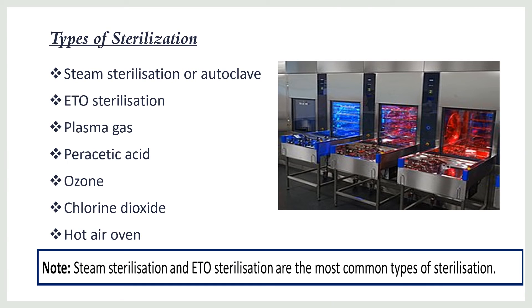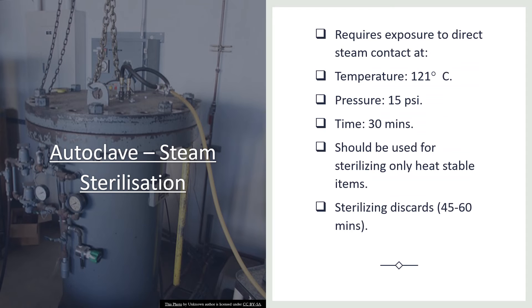Types of sterilization include steam sterilization or autoclave sterilization, ethylene oxide (ETO) sterilization, plasma gas, peracetic acid, ozone, chlorine dioxide, and hot air. Steam sterilization and ETO are the most common. Steam sterilization requires exposure to direct steam contact, temperature of over 121 degrees Celsius, pressure of over 15 pounds per square inch, and timing of 30 minutes. It should be used only for heat-stable items.